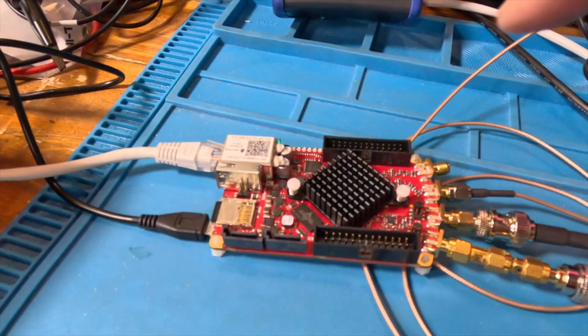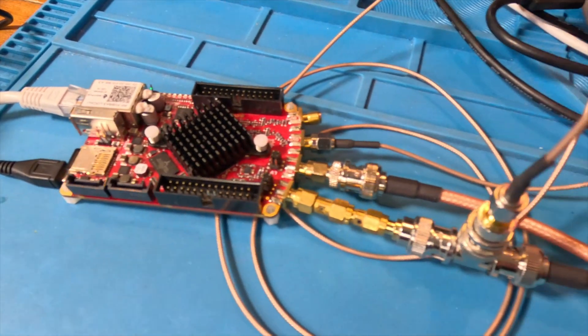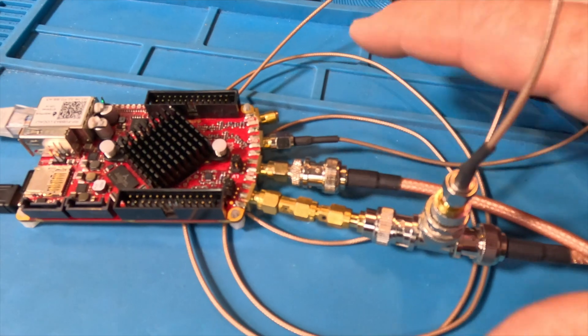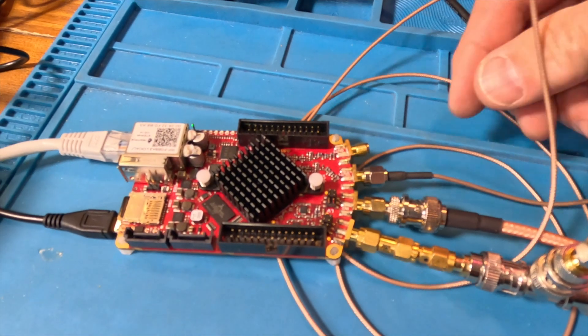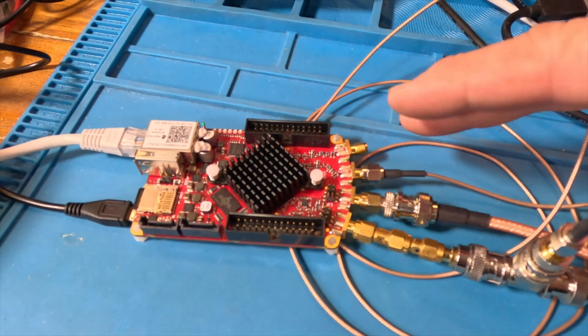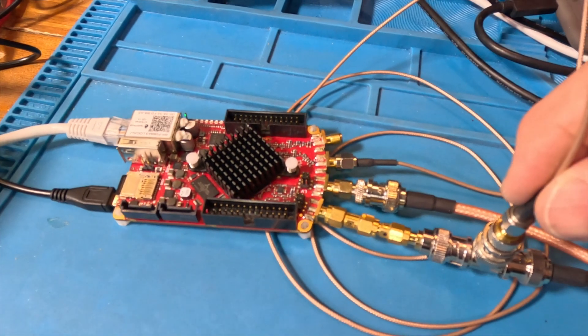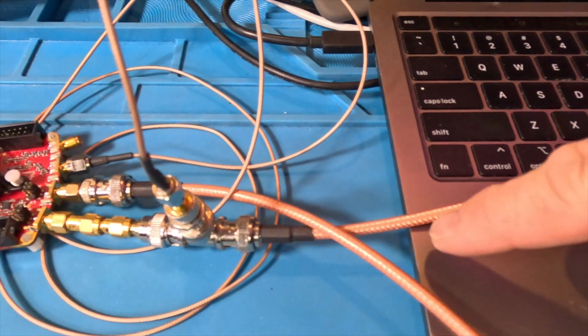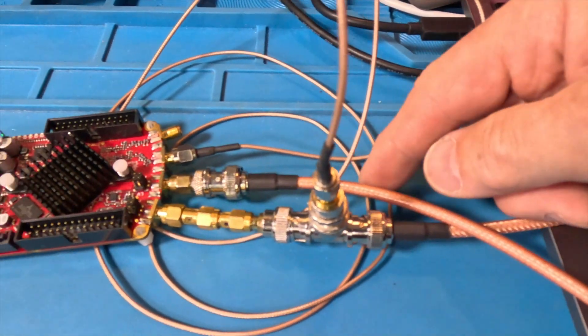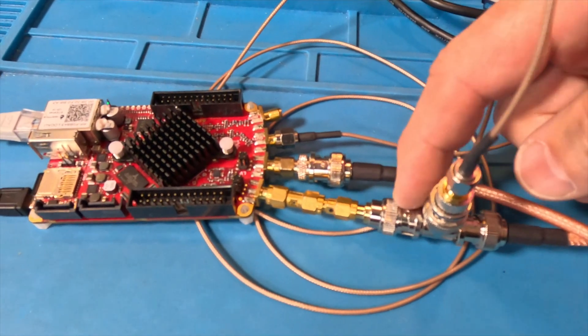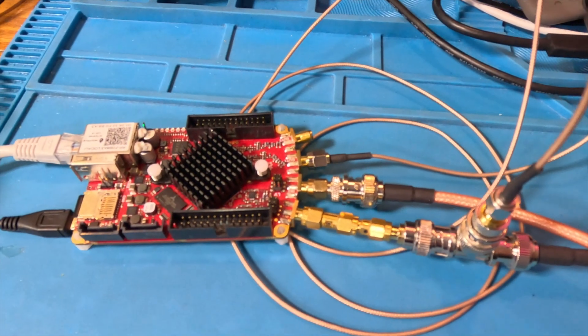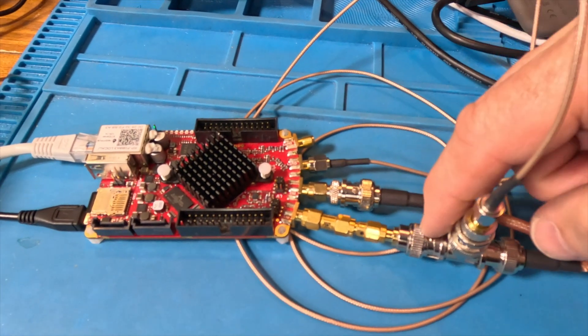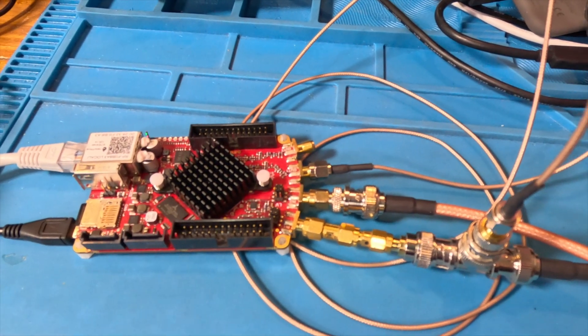All right guys. So I have the Red Pitaya, and this looks kind of messy, but it's actually fine. This cable here is a nice cable, but it's kind of long. So it comes out of output number one, and we're going to calibrate this thing. So I'm taking the input up to here, and this T connection goes to this long cable, and this is actually a really nice cable, and it comes back to input two here. So input one, it just goes directly through this mating connection. So the output signal is going to the coupler and to both channels. So they see the same signal.